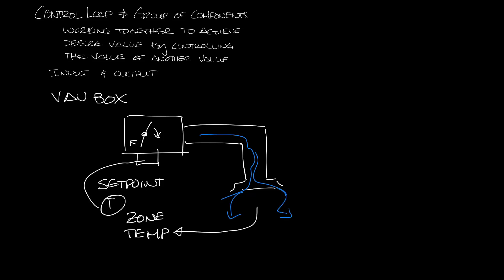So set point and zone temperature are the inputs and the signal going to the actuator is the output. There's another input to the VAV box controller and that's the pressure signal from the flow sensor. So let's draw in an inlet with a flow cross in it and connect that to the controller.